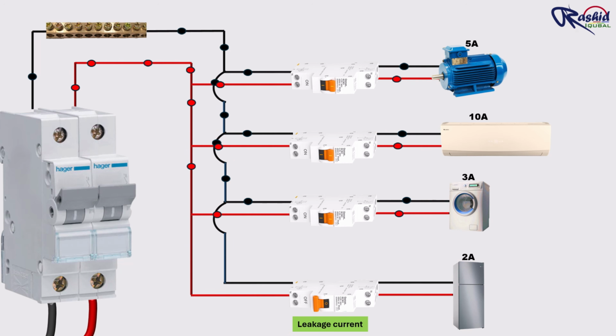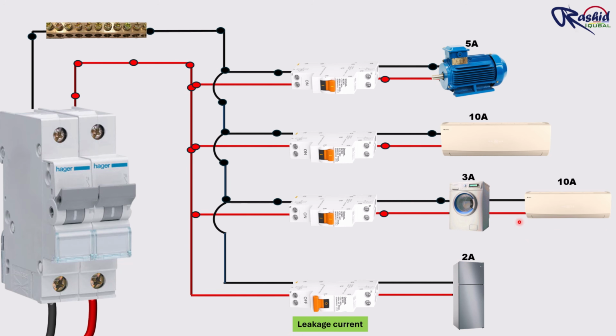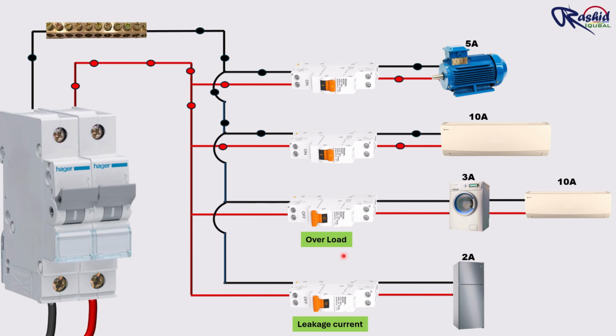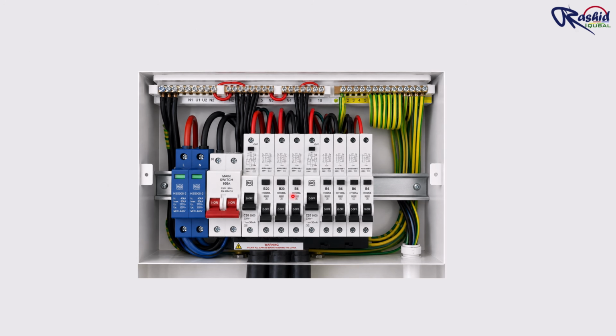Similarly, during an overload condition, the thermal protection inside the RCBO will operate. So this individual protection provides better safety and selectivity compared to using one common RCCB. That is why in modern electrical installations, RCBOs are widely preferred for final circuits. Here you see the example, a single phase distribution board where each outgoing circuit is connected through a separate RCBO. You can see all these are RCBOs and they are connected to separate circuits.